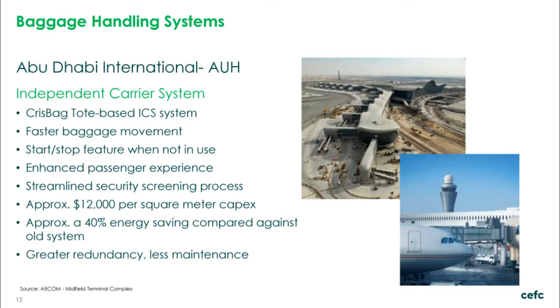The midfield terminal is designed with a maximum capacity of 30 million passengers per year. The independent carrier system will feature 25 kilometres of baggage conveyor belt and is capable of handling 19,200 bags an hour. Through our investigations, we estimate that compared to an older baggage handling system, which has an electrical demand of approximately 520 watts per metre of conveyor, the MTC's baggage handling system will require approximately 124 watts per metre of conveyor. These figures will be subject to change depending on the final build and how the system is operated.